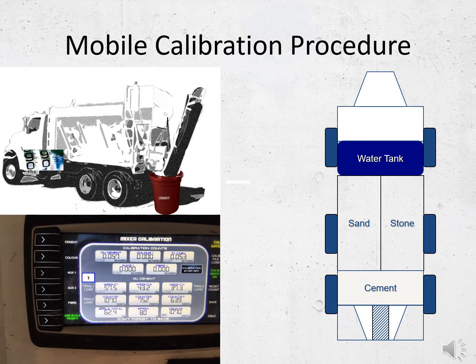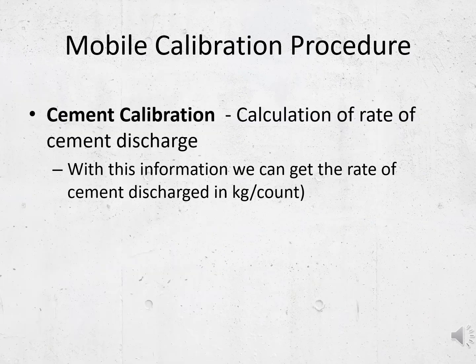Run more if necessary until the unit demonstrates that the variance between the values in a running average of 3 is within the plus or minus 1% batch tolerance limits of Table 23 of CSA A23.1 for cementing materials. Records of historical calibrations should be reviewed annually to verify ongoing compliance with the note to Table 23. The results of your calculations will determine the rate of cement discharge in kilograms per count.